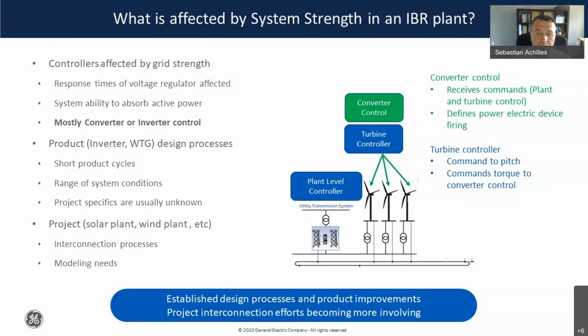There are other controllers, though, that are important to consider. The turbine control would also receive commands from the plant controller related to active power, and will command the pitch control, and it will also command the torque to the converter control. The plant level control will typically try to control, for example, voltage or reactive power at the POI, and frequency or active power at the POI. I imagine you have heard about this before, and it will command the other controllers. As I mentioned, the converter control tends to be most affected by grid strength. The plant level controller, particularly the voltage control, may also be affected, but it's not so involved to solve. Those are relatively simple problems to solve.